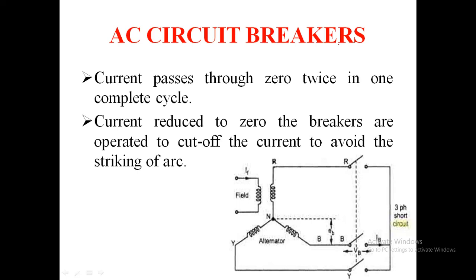The restriking of the arc when current is interrupted depends on the voltage between the contact gap at that instant, which in turn depends on the power factor. The higher the power factor, the less the voltage appearing across the gap relative to its peak value. Before applying this current interruption concept in an AC circuit, some concepts need to be covered for the AC circuit breaker.